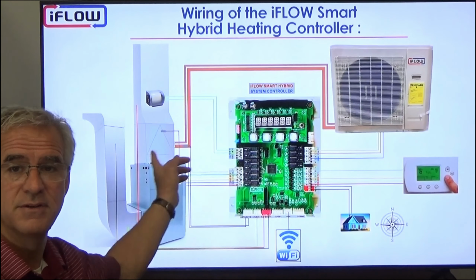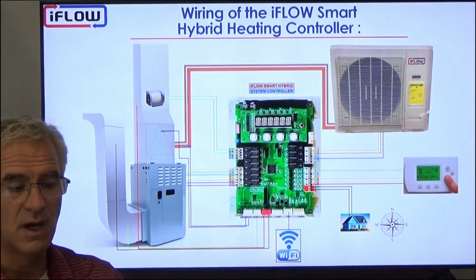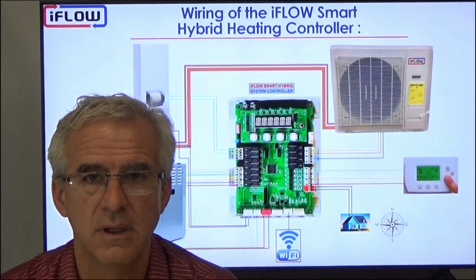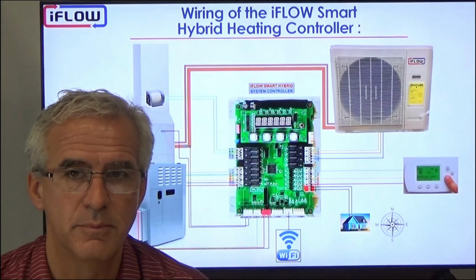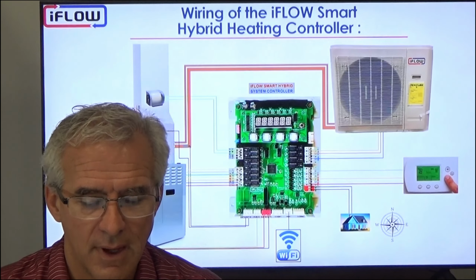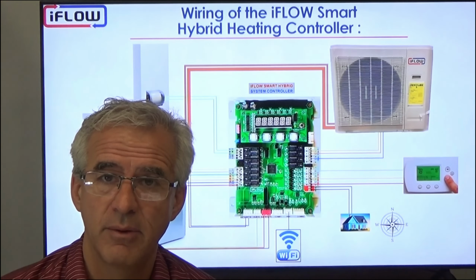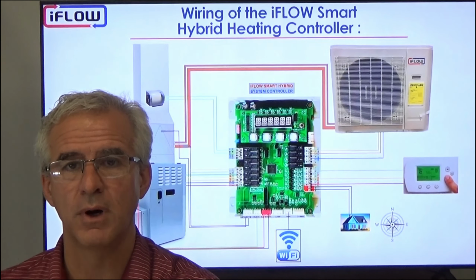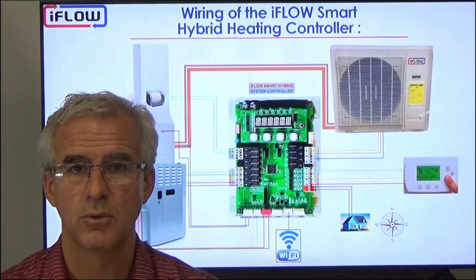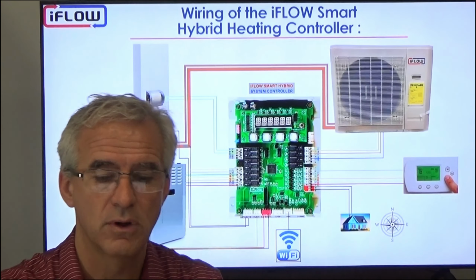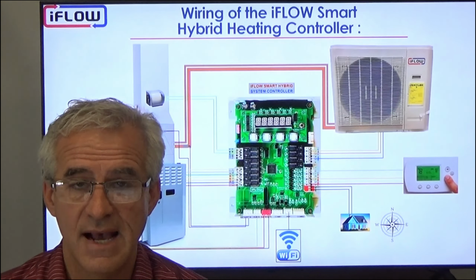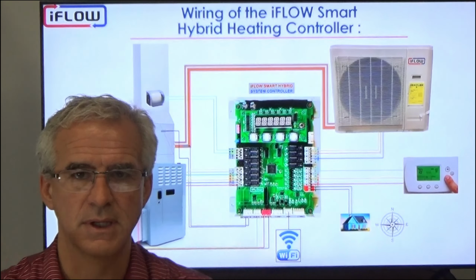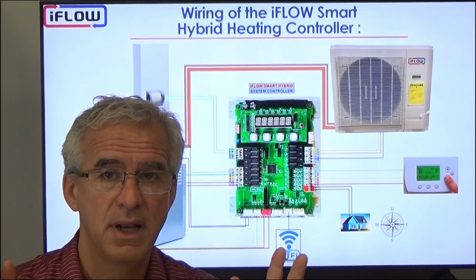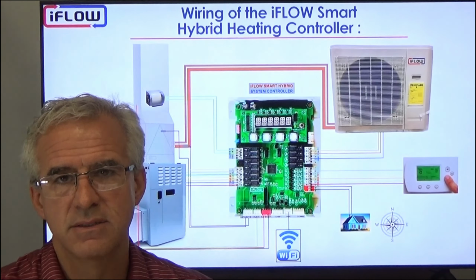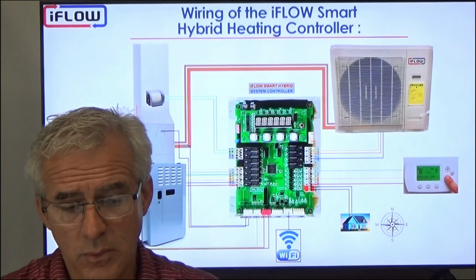So you can run your gas furnace, or you can run the iFLOW hydronic system using the tankless or the boiler as your backup. We can run that for December, January, and February, and then switch back over to the heat pump in March and April. So we're going to run the heat pump for half the season and the gas side for half the season, or something like that, to get a combination, that hybrid heating system. And that's what we're looking at.